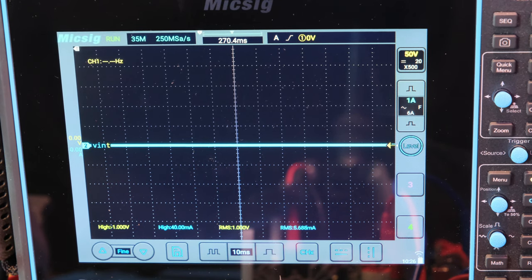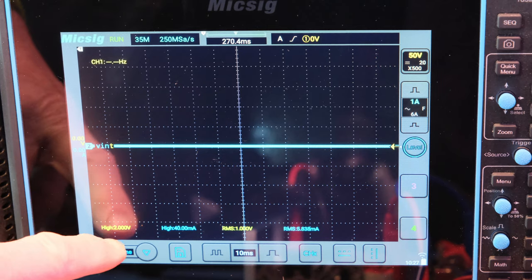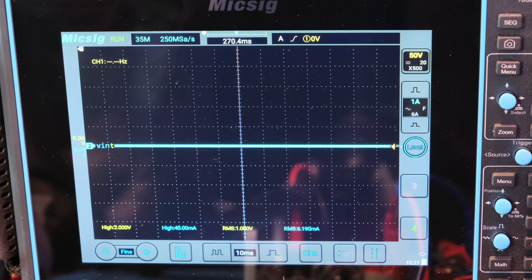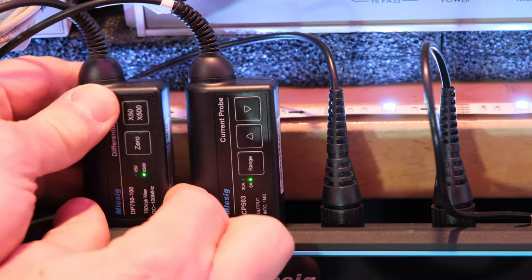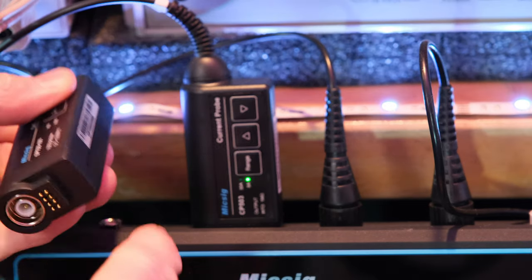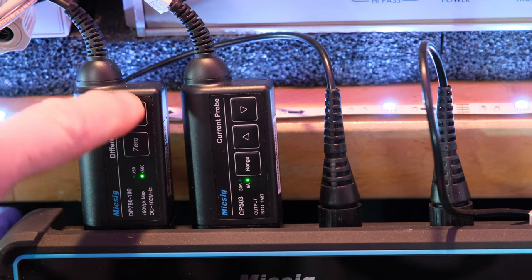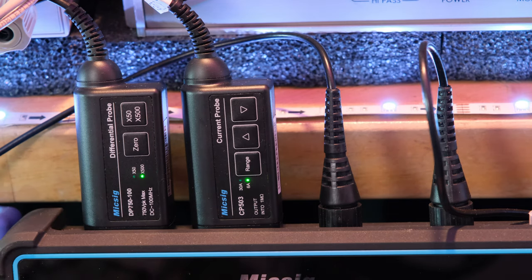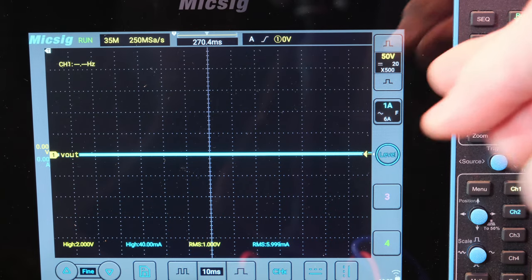So we've got channel one as a differential probe and we're looking at the high and the RMS. Channel two is a current probe, also high and RMS. These are the MicSig probes connected via a magnetic ring. They automatically detect whether you're on times 50 or times 500 via the interface pins. We're set at 50 volts per division and one amp per division.